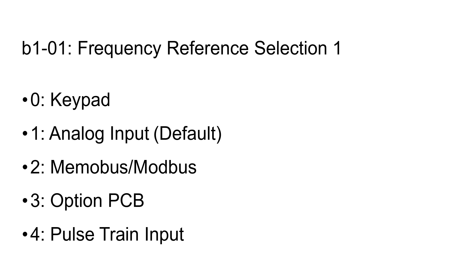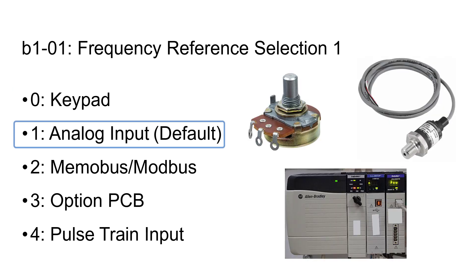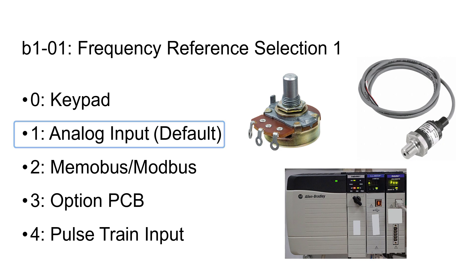The drive has five different ways to input a frequency reference. Setting 0 is the keypad. Setting 1 is an analog input, 0 to 10 volts or 4 to 20 milliamps. By default, the drive looks for a frequency reference from the analog input A1.